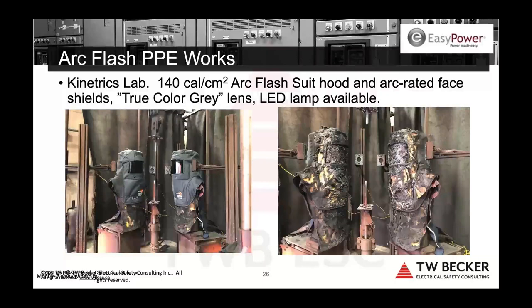Now what you see on the screen are two arc flash suit hoods. These are 140 calorie per centimeter squared ATPV hoods. They're Oberons. And again, I was lucky to be there to witness this, because what was being tested was the true color gray lens technology, to make sure that it passed. All right.